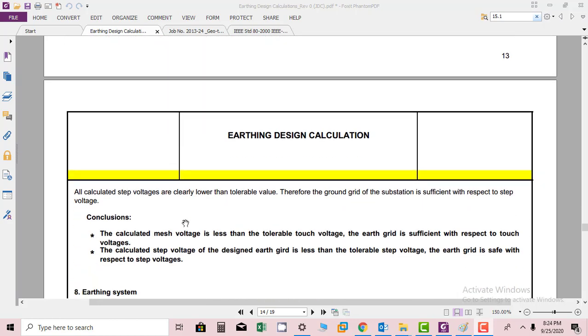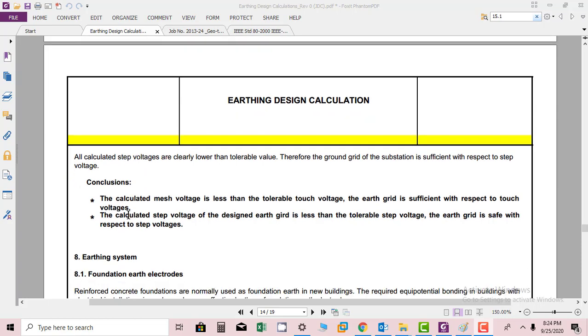All calculated step voltages are clearly lower than tolerable values. Therefore, the ground grid of the substation is sufficient with respect to step voltage.